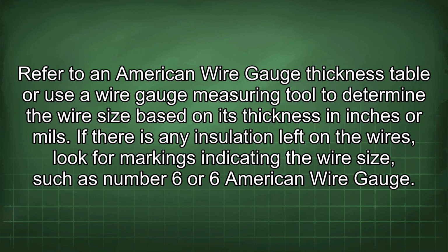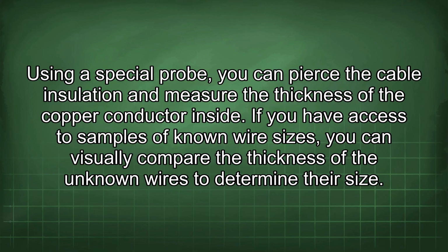If there is any insulation left on the wires, look for markings indicating the wire size, such as number 6 or 6 American wire gauge. Using a special probe, you can pierce the cable insulation and measure the thickness of the copper conductor inside.